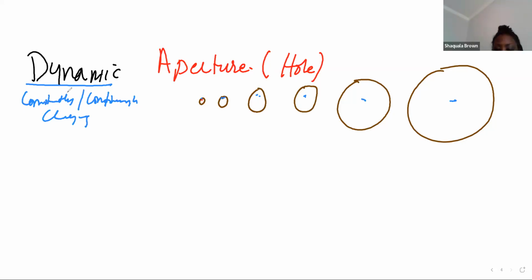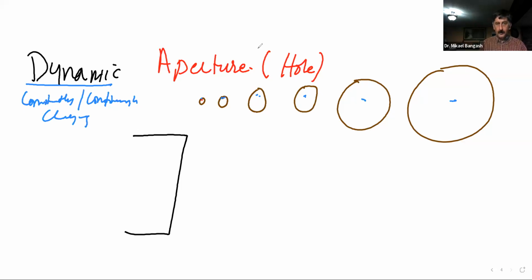Yes. Good. Now just consider that we had a transducer, and we can say it has X, Y, Z number of PZTs. Now the whole point of this dynamic aperture, the primary goal of a dynamic aperture, was mainly to improve the lateral resolution. Improve the lateral resolution by what? By decreasing lobes.